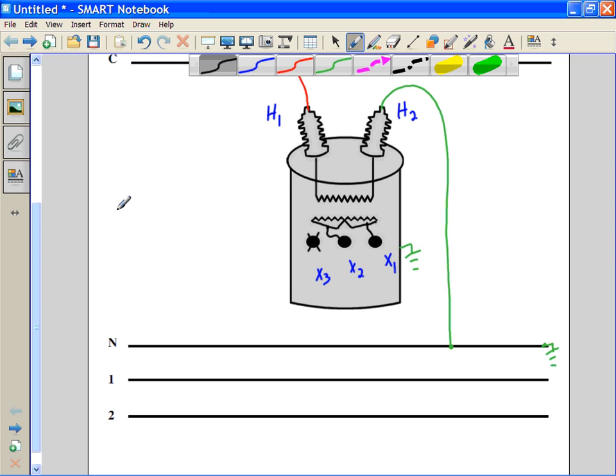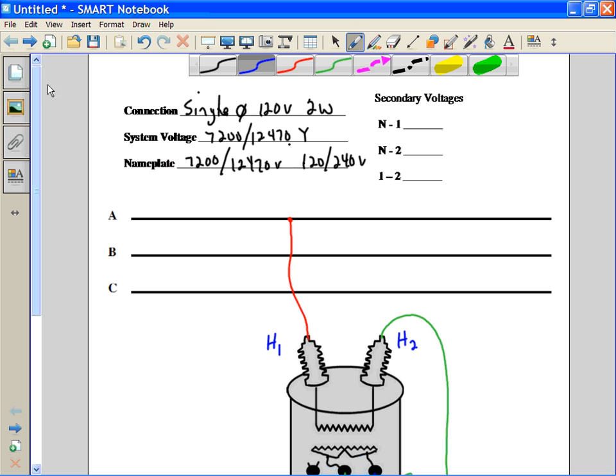And now we have a coil wired so that the only voltage we can get out of the secondary side of this transformer is 120 volts. So to finish off our connection on the secondary side, X2 is typically used as the neutral wire. So we'll connect X2 to the neutral, and we've only got one other bushing that we can make a connection to. That would be X1, and I'll just bring it down to line 1. So the only voltage potential we have in this case is between the neutral and line 1. So that voltage is 120 volts, and these two in this case just aren't being used.